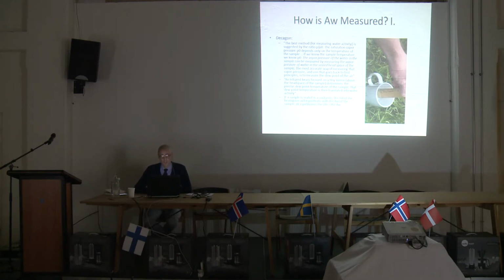That's water activity. And the most simple thing they can say about it is, in a sealed container, the relative humidity of the headspace will equalize with the water activity of the sample. So as the temperature stabilizes and becomes uniform, then you will start to see that vapor pressure equalize with the relative humidity. Relative humidity will equal water activity at that point.